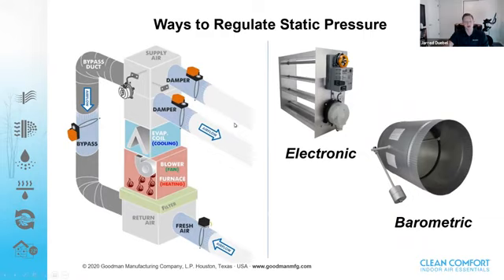So when you're regulating static pressure on the traditional type system, you're going to want to use either electronic or barometric type bypass damper. Again, that's traditionally going to be installed right here in a section of your bypass duct, and you're going to make sure that you set either that weighted blade or that static pressure sensor for the electronic bypass damper to alleviate static pressure at a specific threshold.